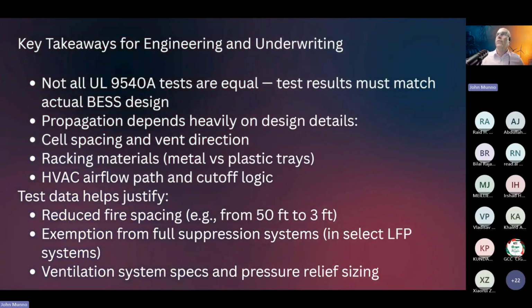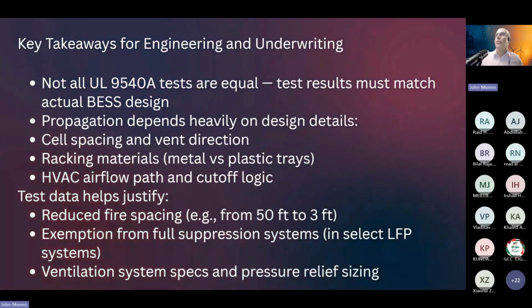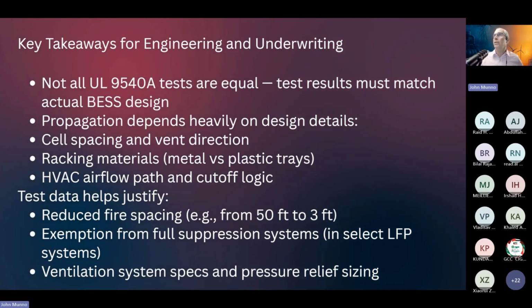All right. So the key takeaways for engineers and underwriters is that not all 9540A tests are equal. The results must match the actual BESS design. You can't just use the fact that this manufacturer's Model A was tested. Now we're going to install Model B or C or D, and you have to test exactly what you're installing. And the propagation depends heavily on the spacing and the vent direction. So we've seen vent designs where the side of a module has a vent installed, or the top of the module has a vent installed.